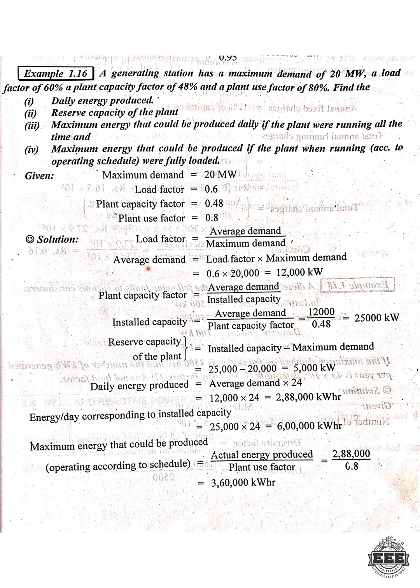Next, we find the installed capacity. The formula uses the plant capacity factor: installed capacity equals average demand divided by plant capacity factor. So 12,000 divided by 0.48 gives us 25,000 kilowatts. That is the installed capacity of the plant, which is 25,000 kilowatts.